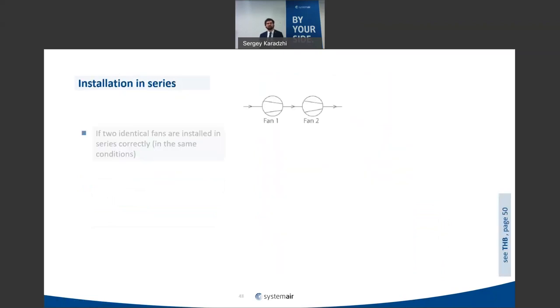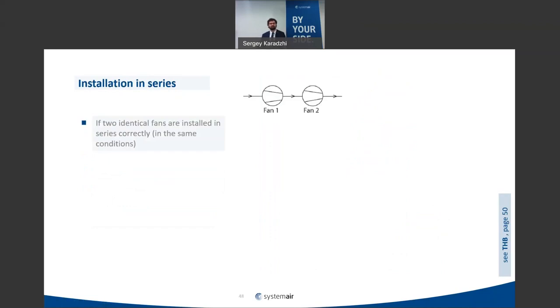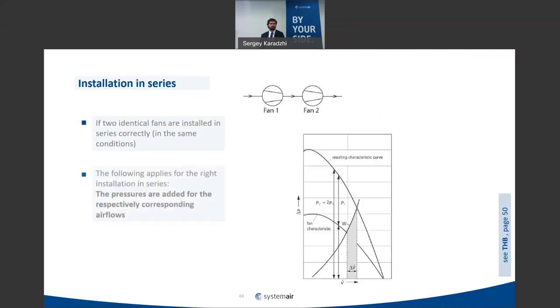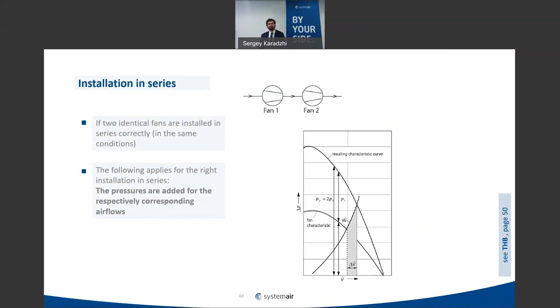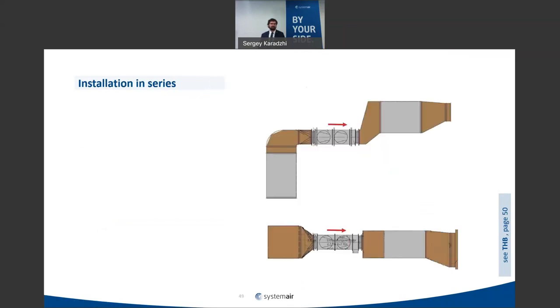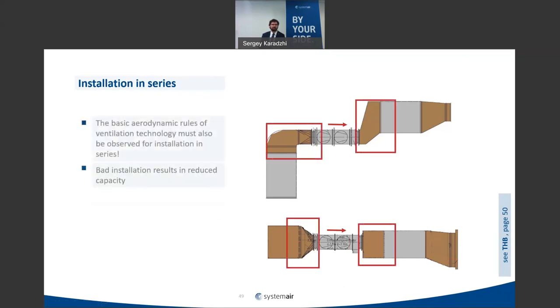In series installation, as with a single fan: if the installation conditions are poor, the curve will not be what you expected. In conclusion, to make an energy-efficient ventilation system, you need to optimize your duct system — reduce pressure losses in all components. We can make a very efficient fan, but if it is installed in a poor system, the overall result suffers. Only after optimizing pressure losses should you select the right fan for your system.